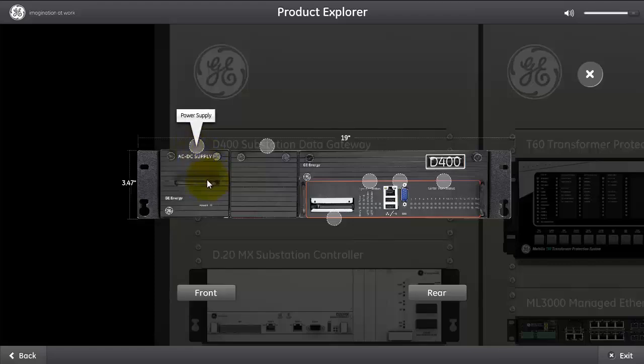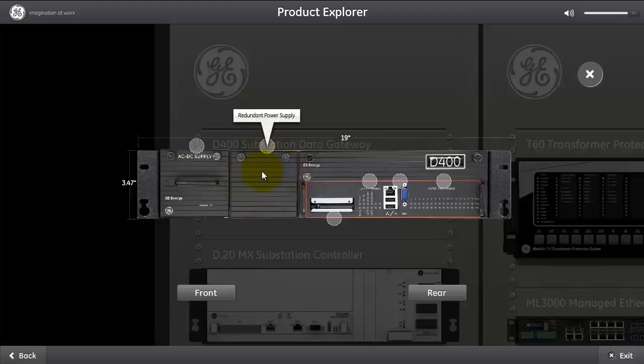The power supply in the D400 is a redundant power supply and there's sensors on the back where it will allow you to sense when power is lost to provide an alarm on D400 power loss. The redundant power supply can be either 100 to 240 volt AC, covers 47 to 63 hertz, or 100 to 300 volt DC, plus or minus 10%. The other choice is 20 to 55 volt DC. You can have any combinations of these redundant power supplies in the same D400.